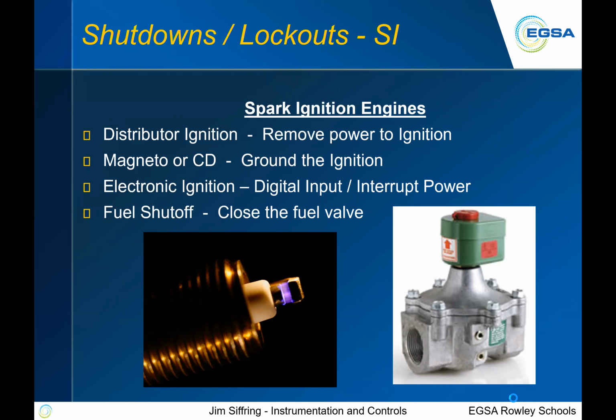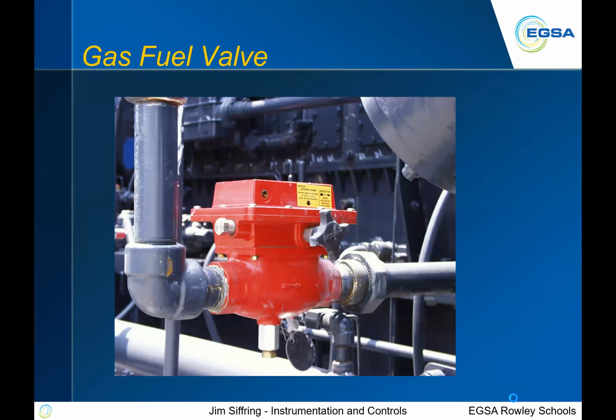If it's electronic, we can just interrupt the power or give it the digital input to shut off. In some cases, maybe we want to shut the fuel off, so we close the fuel valve. That device on the right is a fuel valve. We can just tell it to close. Here's another fuel valve, very similar, just that's what they typically look like out in the field.